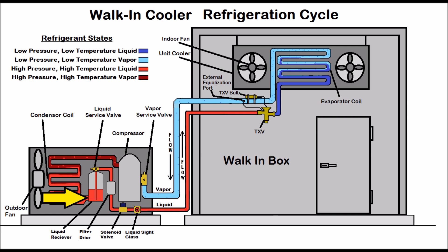The liquid receiver is a storage vessel for the sub-cooled liquid. The amount of liquid in that receiver has a direct correlation to how cold the walk-in box is. If it's very cold in the walk-in box the system doesn't need as much liquid refrigerant, so it's stored in the receiver. When you first start a walk-in box up, that liquid receiver should be drained almost all the way down, and you should have a solid column of liquid heading through the liquid sight glass — verifying you have enough sub-cooled liquid heading to the TXV. You don't want to add extra refrigerant that will simply be stored in the liquid receiver.